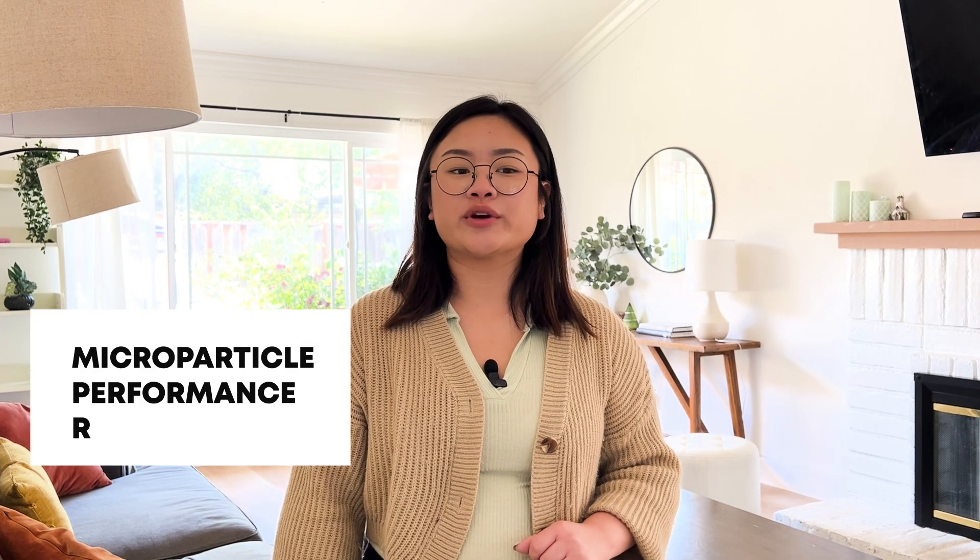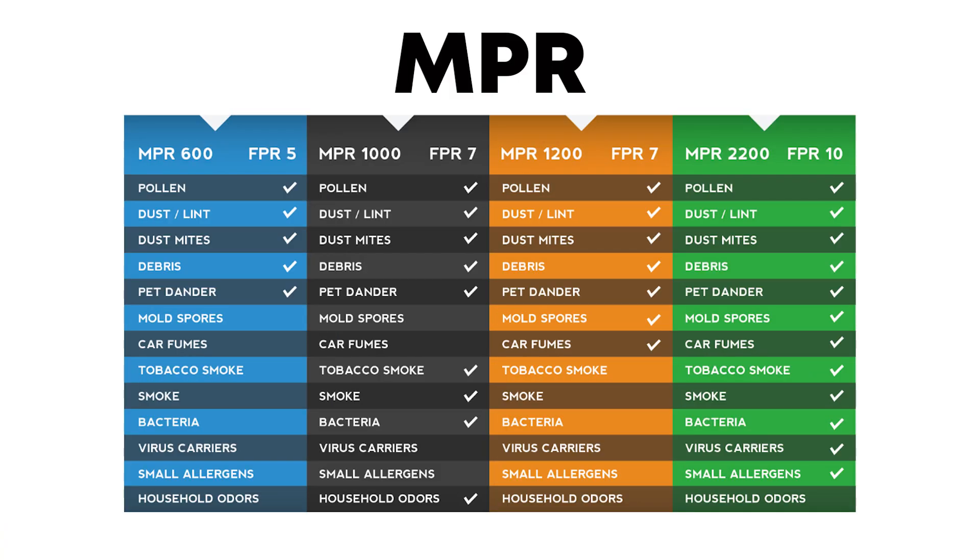MPR ratings range from 300 to 2200. The higher the number, the better it is at catching particles. MPR 600 filters can capture dust, lint, debris from dust mites, pollen, and mold spores. This is similar to a MERV rating of 8 and FPR 5.